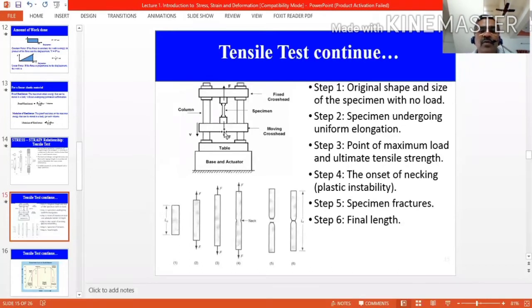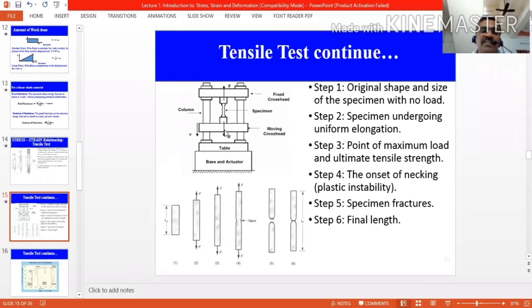The downward motion is given at a velocity of one millimeter per minute — this is the standard value. Generally for a standard tensile test we give a velocity of one millimeter per minute, as per ASTM standard. The load is applied and our objective is to produce elongation at one millimeter per minute velocity.